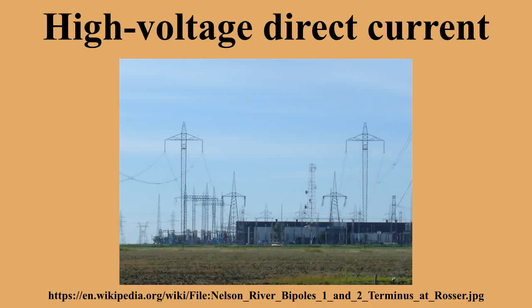Disadvantages. The disadvantages of HVDC are in conversion, switching, control, availability, and maintenance. HVDC is less reliable and has lower availability than alternating current systems, mainly due to the extra conversion equipment. Single-pole systems have availability of about 98.5%, with about a third of the downtime unscheduled due to faults. Fault-tolerant bipole systems provide high availability for 50% of the link capacity, but availability of the full capacity is about 97% to 98%. The required converter stations are expensive and have limited overload capacity.